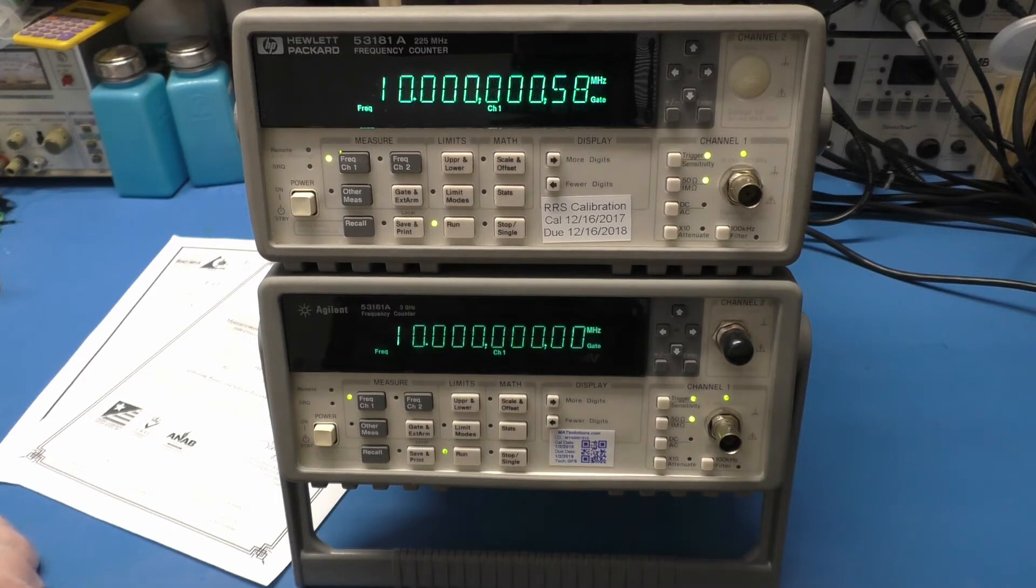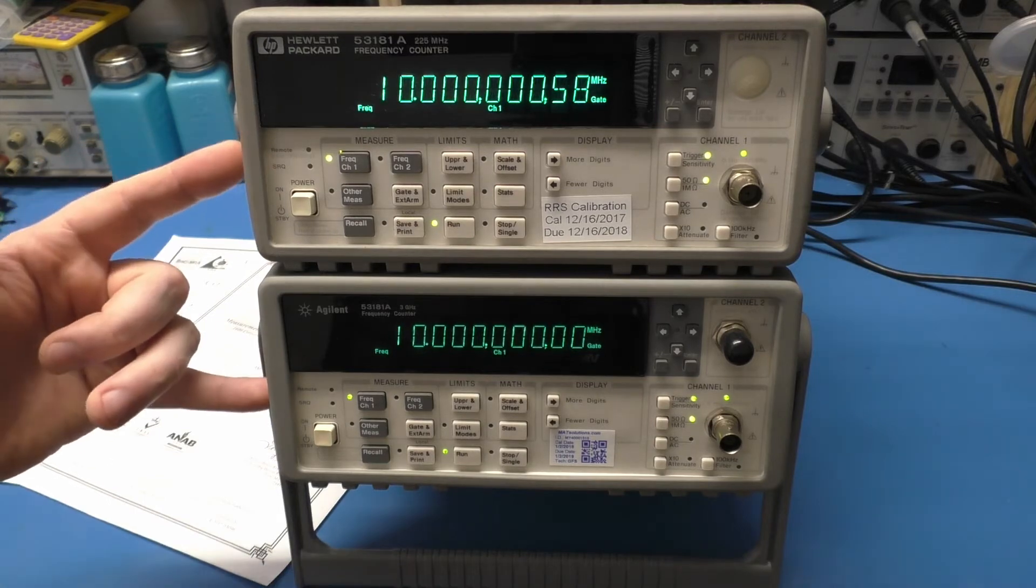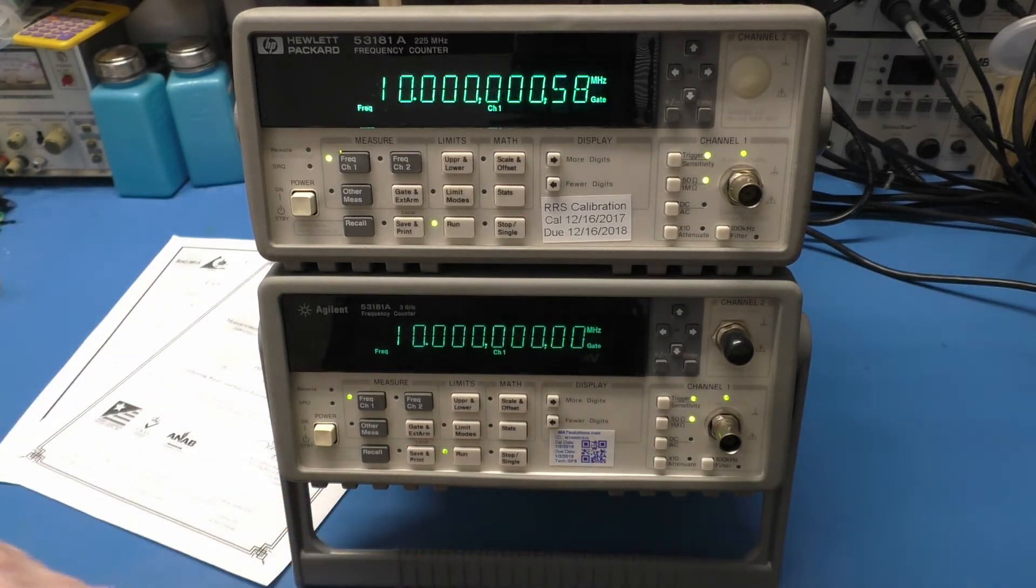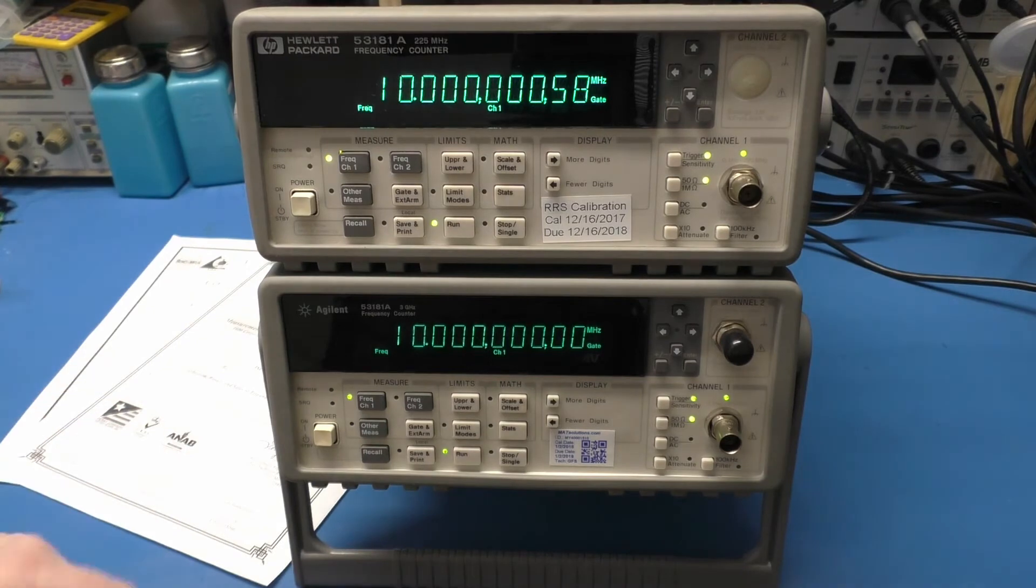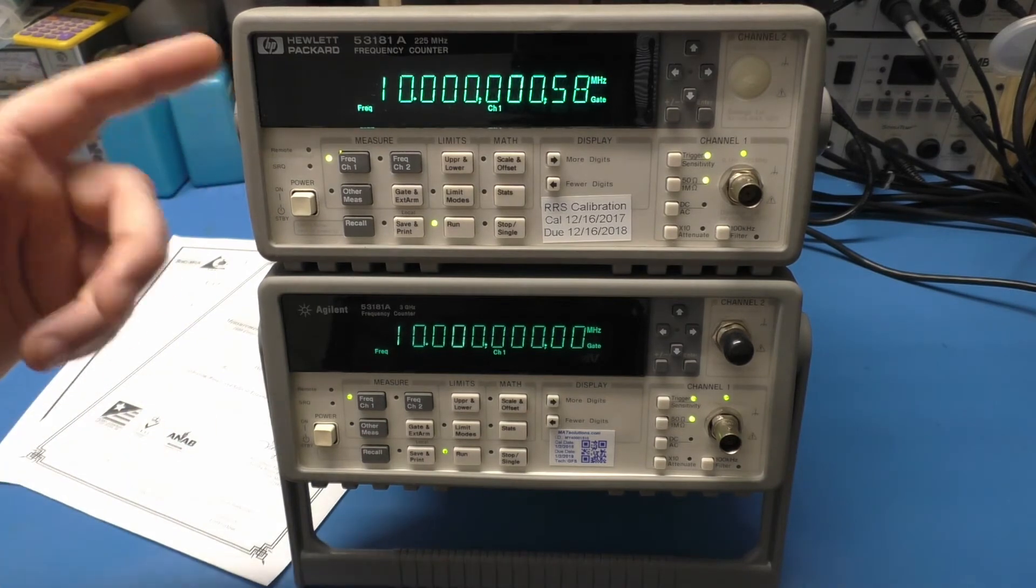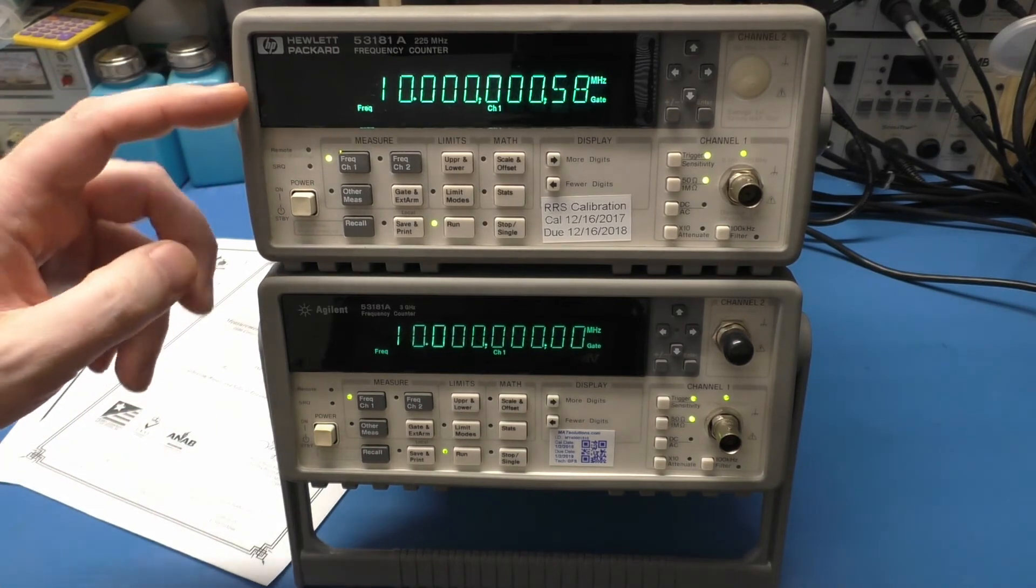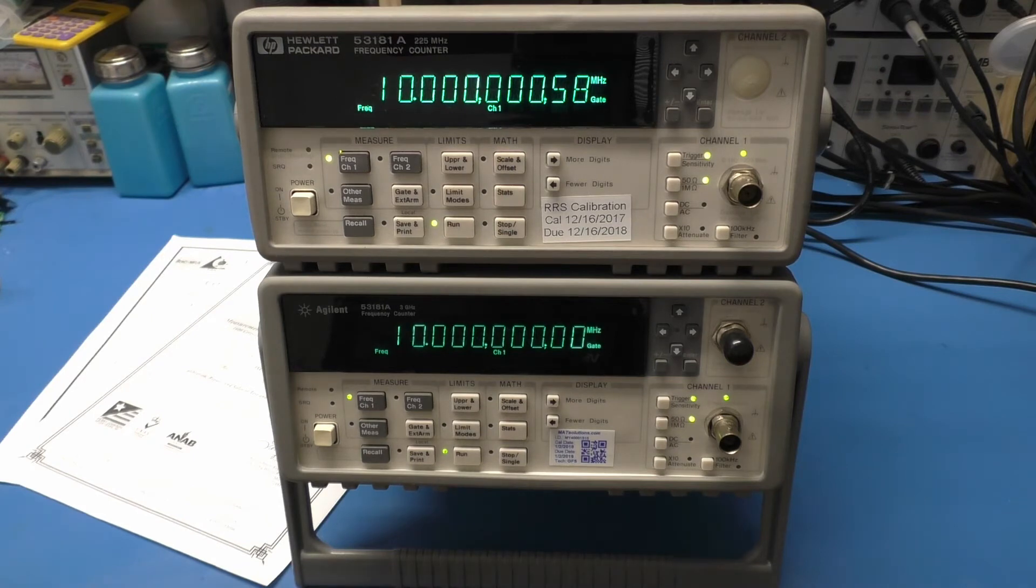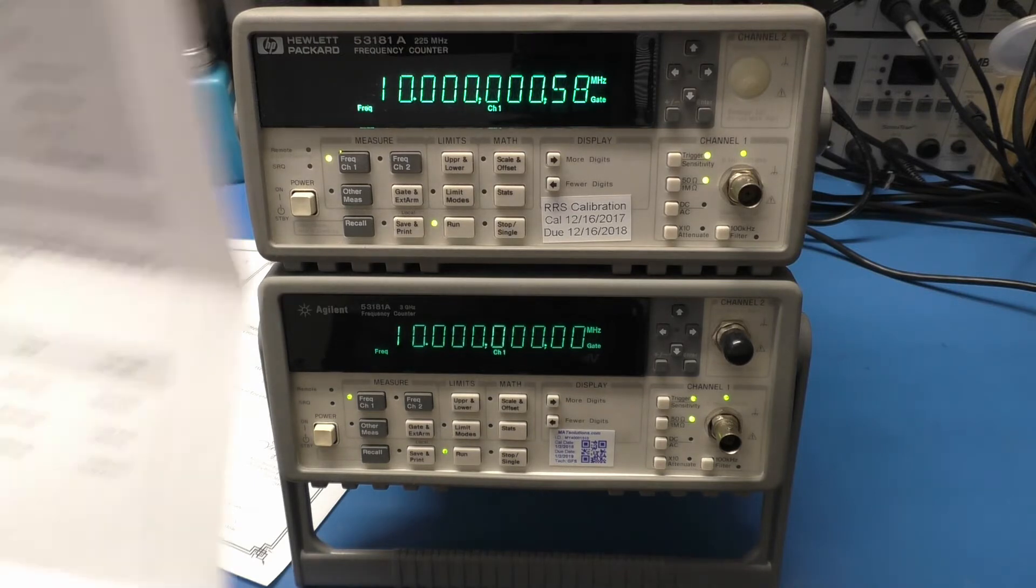As you could see, I plugged in my GPS disciplined oscillator into these counters. The one that was cal'd by the Good Lab, we agree. This one, we don't. I have no idea what they used for this. Let's take a look at the certificates and see if they're even worth the paper they're written on. Because again, anybody can make a certificate just like anybody can make a sticker.